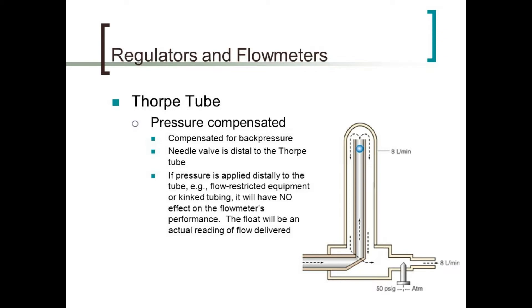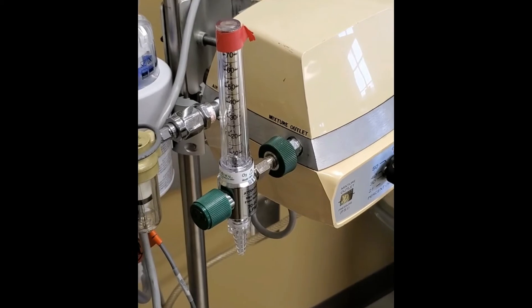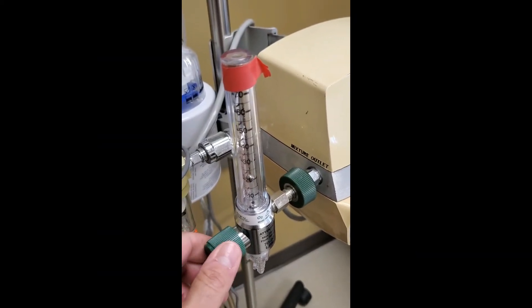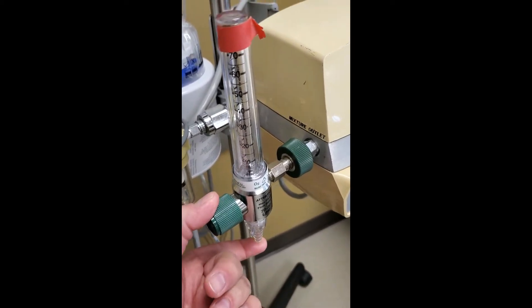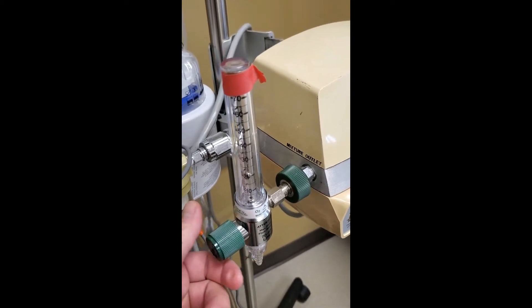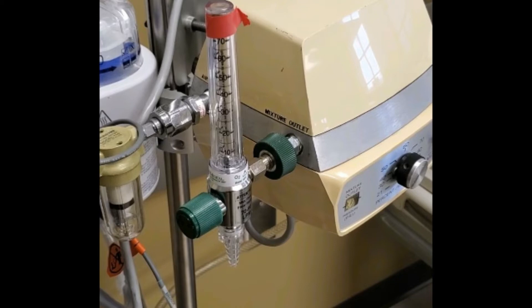In order to do that, you need a special thing that many of you may not realize is special — you probably all have them or have access to them — and that is a compensated Thorpe tube flowmeter, seen in the picture here. What makes these special is that they show you the true downstream flow by allowing some air to bypass on the inside, so when that little ball is riding up and down in the chamber, it's actually showing you what the flow is downstream. You can see that if you cut the flow off, it drops to zero.